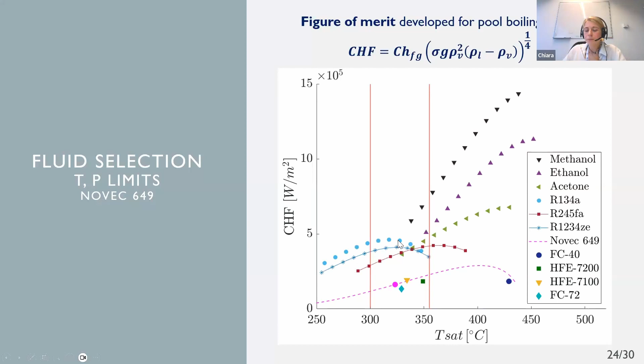Methanol, ethanol, and acetone had some flammability issues. So among different NOVEC refrigerants, we decided to go with NOVEC 649 because it has a saturation temperature, indicated by this dot, of around 49-50 degrees at ambient pressure. It also has a very low global warming potential, below 1. That was something we had to consider.